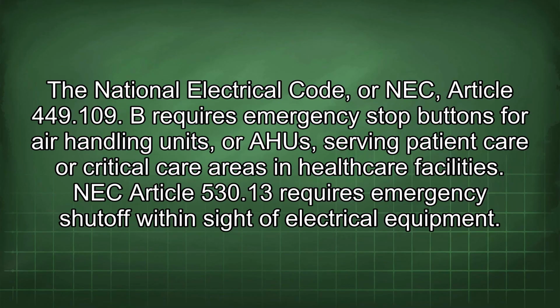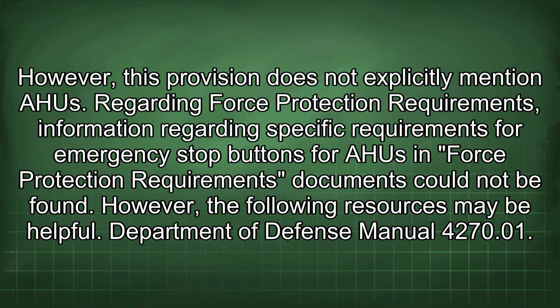The National Electrical Code, or NEC, Article 449.109.B requires emergency stop buttons for air handling units, or AHUs, serving patient care or critical care areas in healthcare facilities. NEC Article 530.13 requires emergency shutoff within sight of electrical equipment. However, this provision does not explicitly mention AHU.